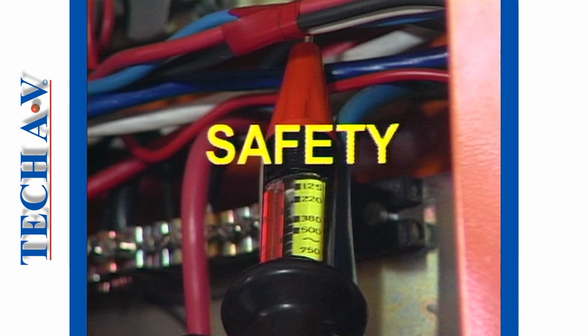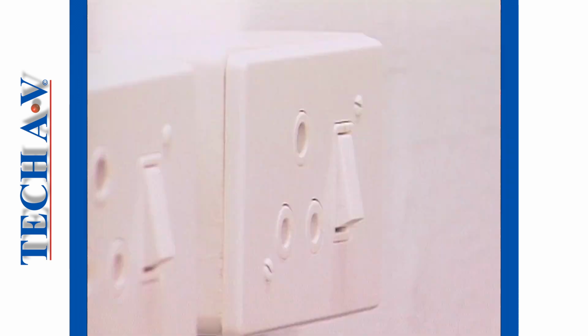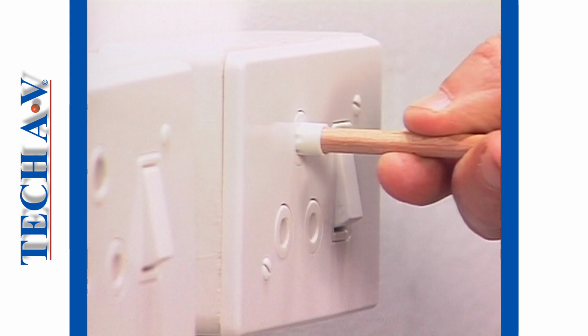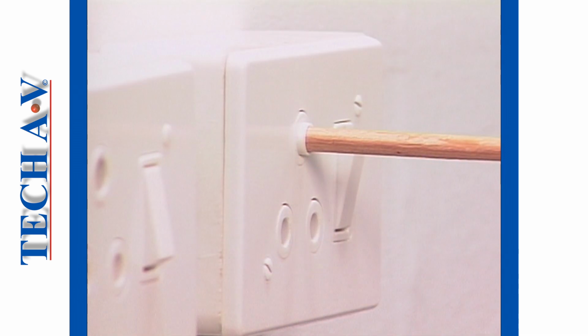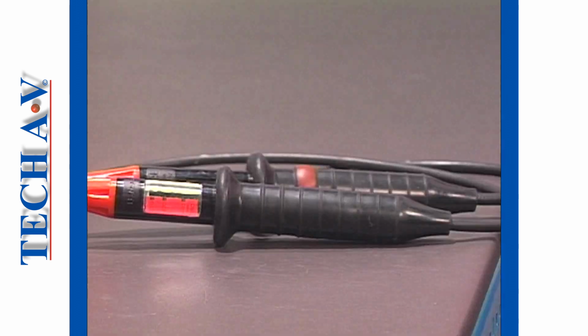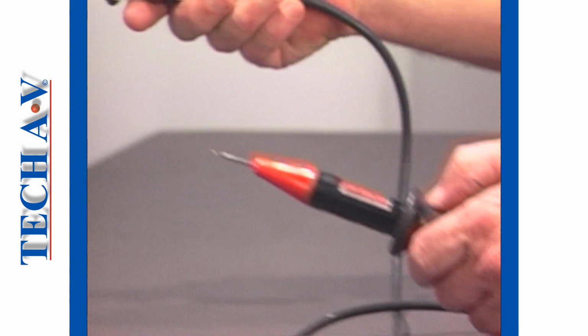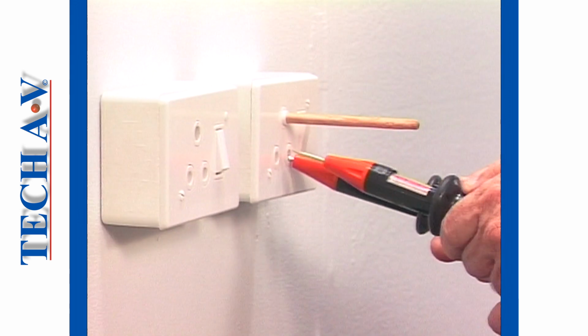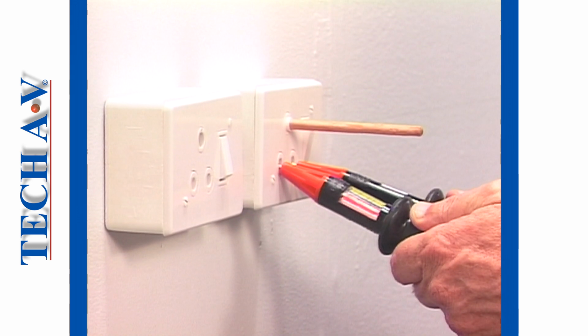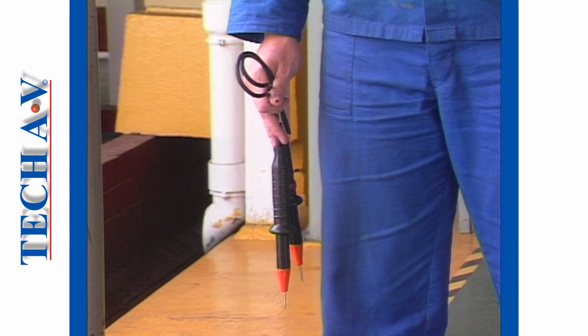A few pertinent points regarding the safe usage of probe testers are now in order. Always use a non-conductive probe to open a safety guard on sockets. A plastic or wooden probe is safe to use. The tester should always be held by its insulated handles. Never let your fingers contact the probes. Always keep the probe points away from your body. Carry the tester in your hands. Don't hang it around your neck, as this could lead to an accident.